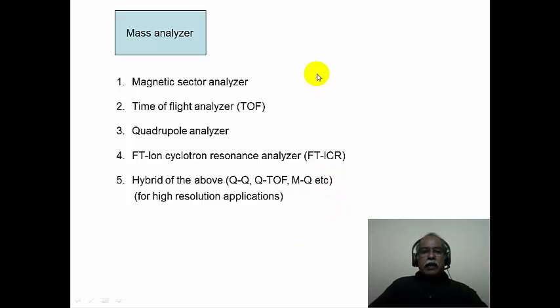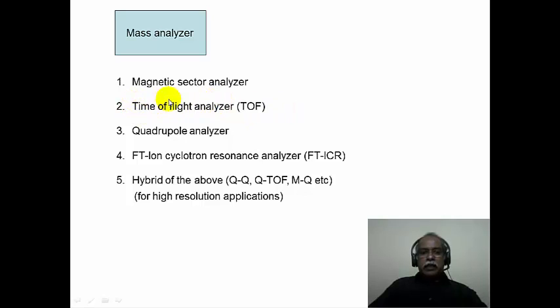Once ions are produced, they are analyzed in an electric sector or magnetic sector analyzer. Magnetic sector analyzers are very common; ions are separated based on their mass-to-charge ratio. One can also use a time-of-flight (TOF) analyzer, where heavier ions travel slower and smaller ions travel faster. A quadrupole mass spectrometer is another option, and ion cyclotron resonance — a very sensitive Fourier transform technique — is also commonly used. Combinations of these analyzers are used in hybrid mass spectrometers.